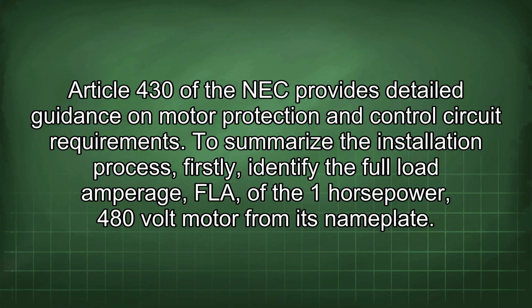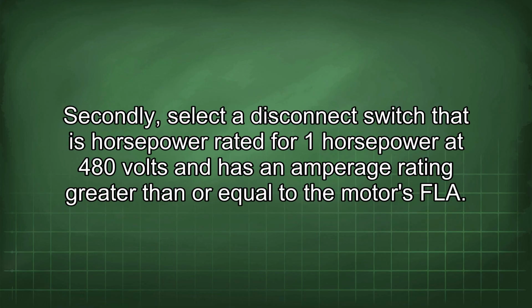To summarize the installation process, firstly, identify the full load amperage, FLA, of the 1 horsepower 480 volt motor from its nameplate. Secondly, select a disconnect switch that is horsepower rated for 1 horsepower at 480 volts and has an amperage rating greater than or equal to the motor's FLA.